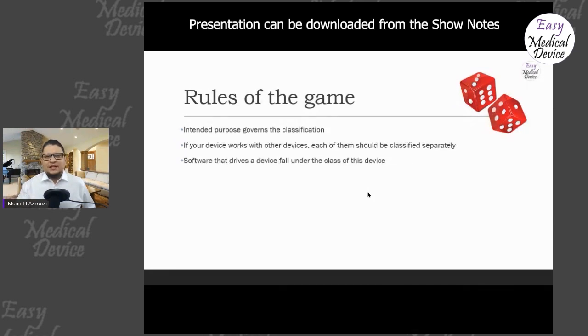If the device is class 2A, but it's controlled by software, the software is also class 2A. If it's software by itself, so it's an application or software, what we call software as a medical device, then it's classified on its own. It's not classified because it's on this machine or that machine, it's classified on its own.